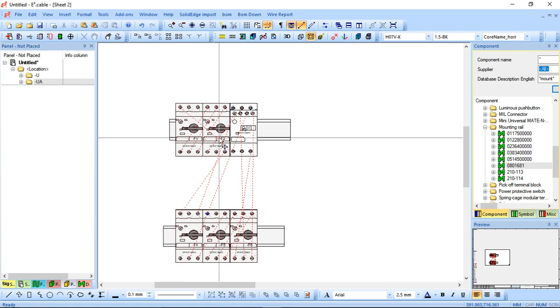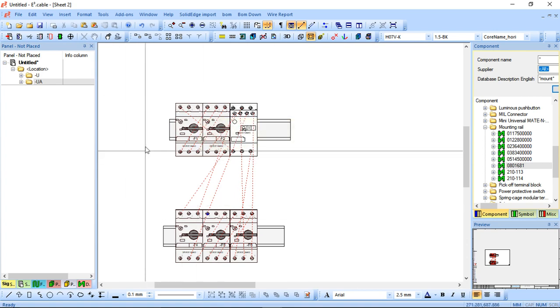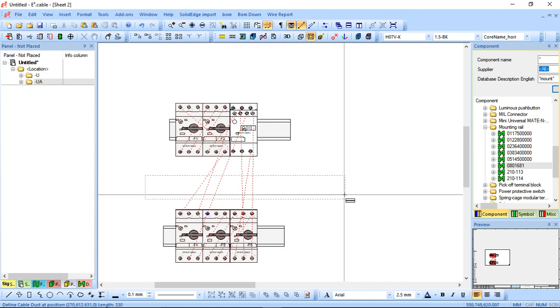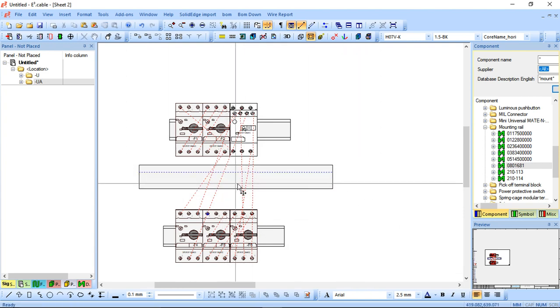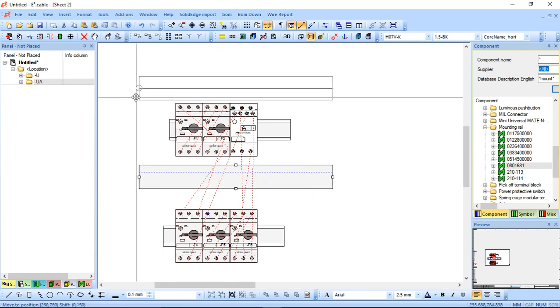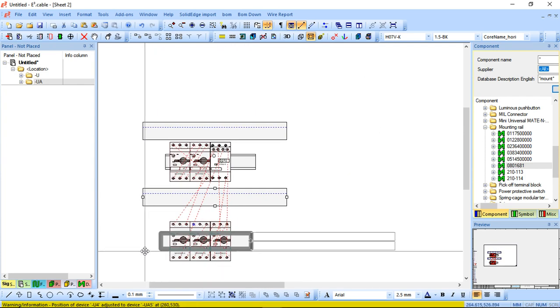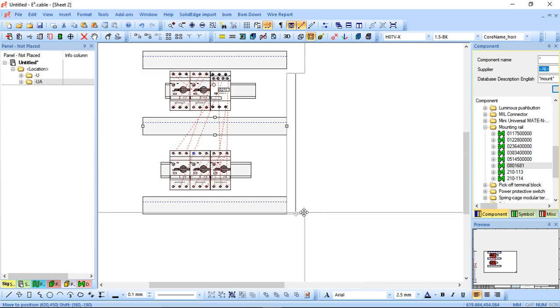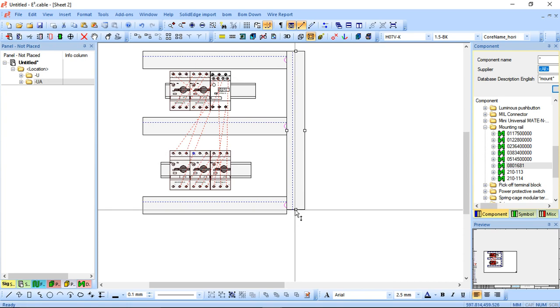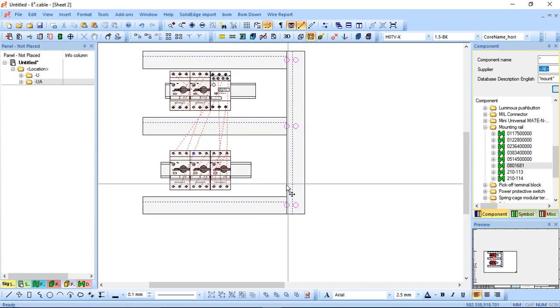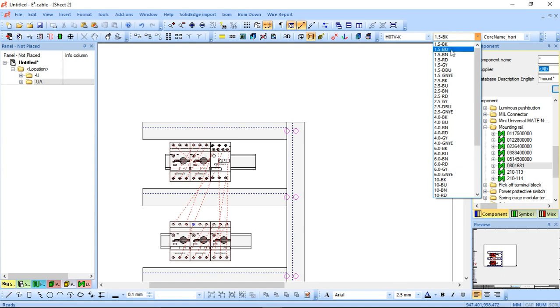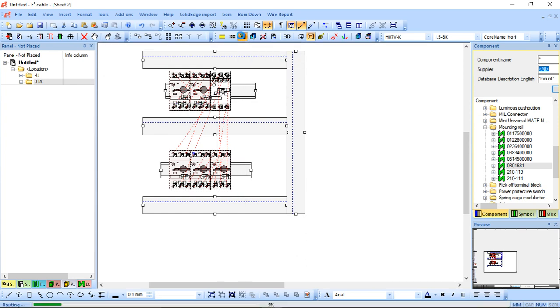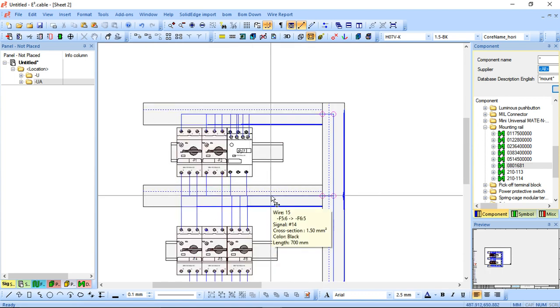So you see all my red dotted lines actually showing me that these are connected from my schematic — from this to this. What you can do is actually automate that further. I'm just going to create a cable duct and put it in now quickly. I'm going to copy some over to make life easy — I'll put one there and one below. It's going to tell me when there's an interference because it's a physical, not a schematic anymore. So I'm just going to place that here and extend them over. All I need to do now is have the correct cable gauge selected, highlight everything, and click the auto-connect function.